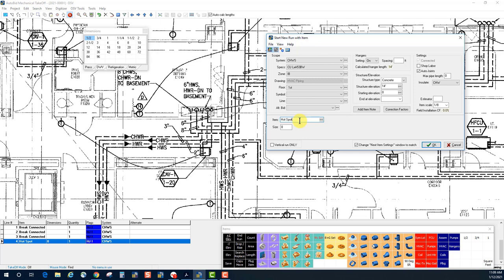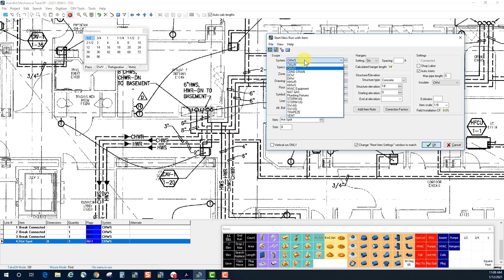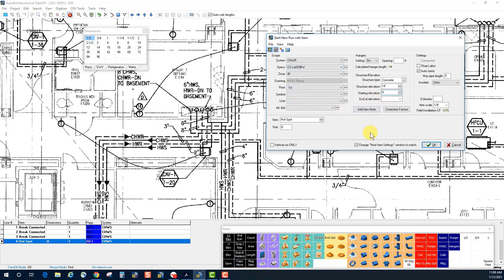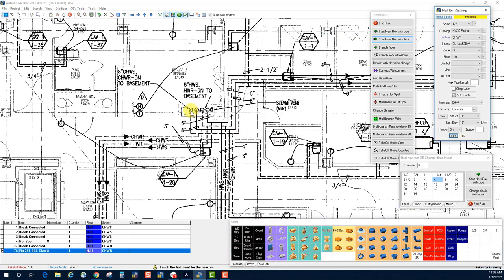I'm going to work on this particular part of the drawing. We can see this is an eight-inch chilled water return down to the basement, and we're on the first floor, so this is a vertical pipe before it becomes horizontal. My starting elevation is going to be zero because I'm going from the floor up, and I'll continue horizontal at 12 feet — that's the end at elevation command. I'm starting with a riser clamp, size eight inch, then clicking where that pipe comes up from the basement.